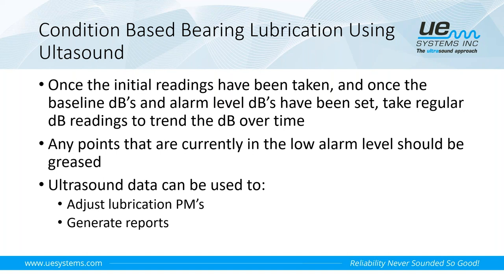So once these initial readings have been taken, once the baselines have been set, we're going to be trending the decibel level over time. And then any points that are currently in the low alarm status would be the points that we apply grease to. So again, instead of going out to grease everything like we normally would on a time-based lubrication PM, we let ultrasound let us know when it's time to be greased. And again, that's going to be points that are currently in the low alarm status. And we can use this data now to generate reports.